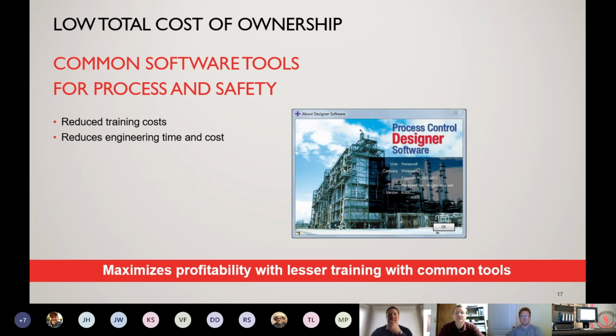You can actually create your own library as well. Let's say you had a 3-element boiler control, and you had a series of 10 function blocks connected together in the programming. You can save that whole function block sequence as part of your library. Later on, when you want to redevelop or add a process, you can select that single function block from your library, drag it onto the screen, and program the HC900, which really reduces a lot of startup and engineering time.